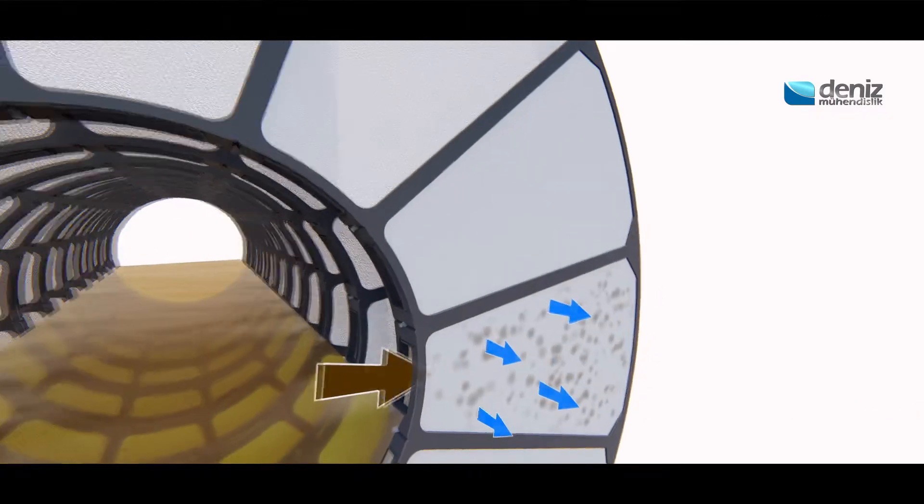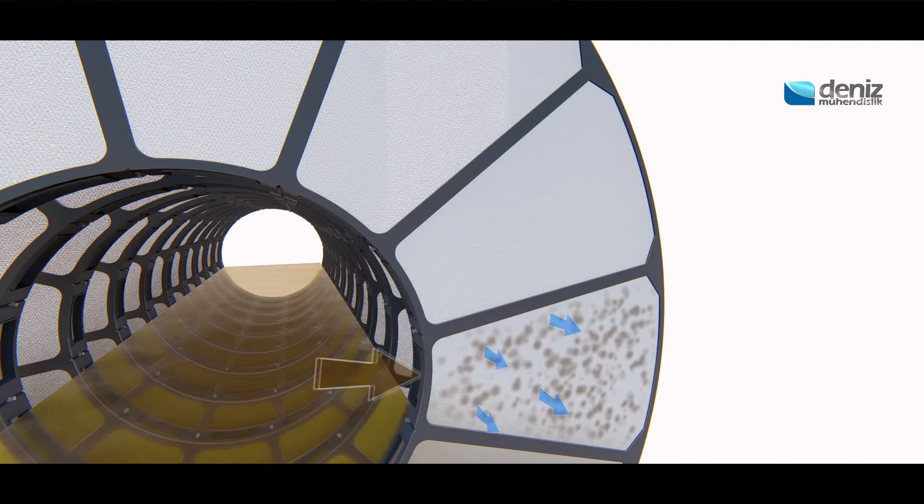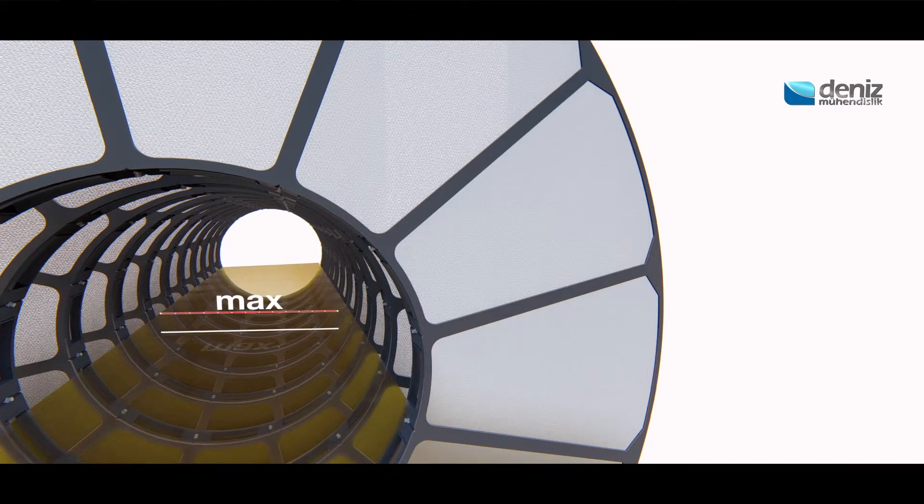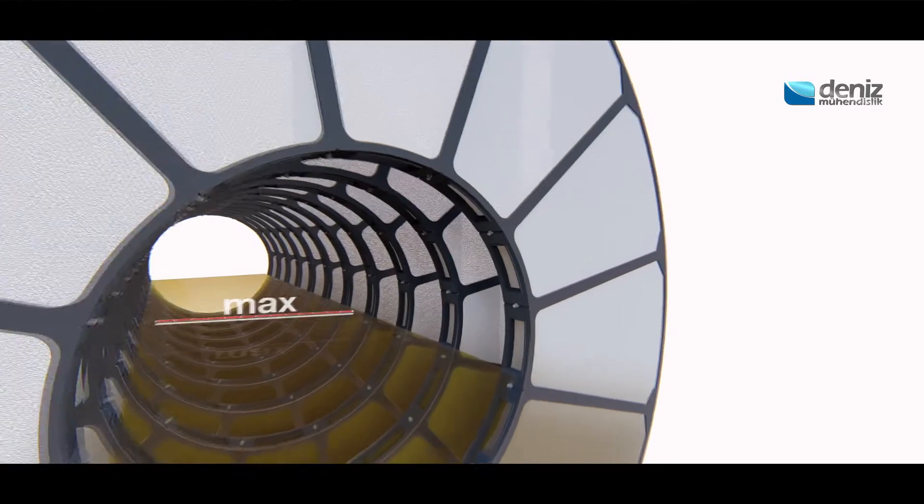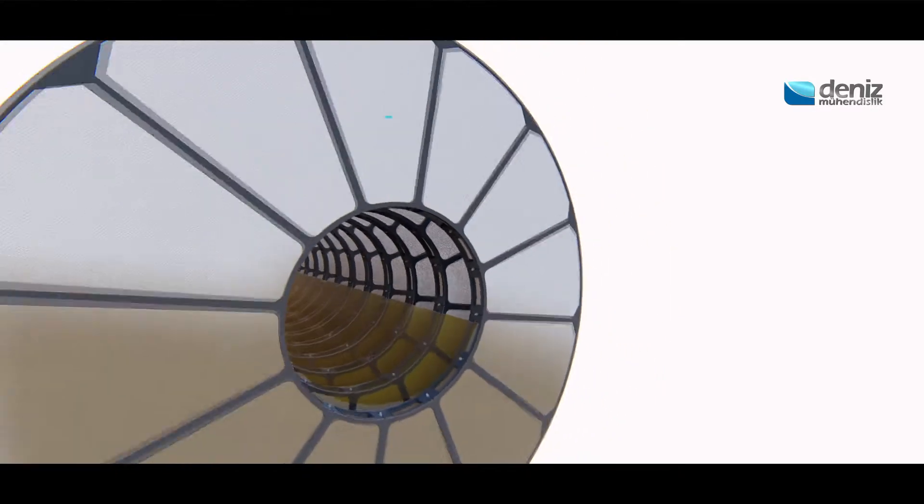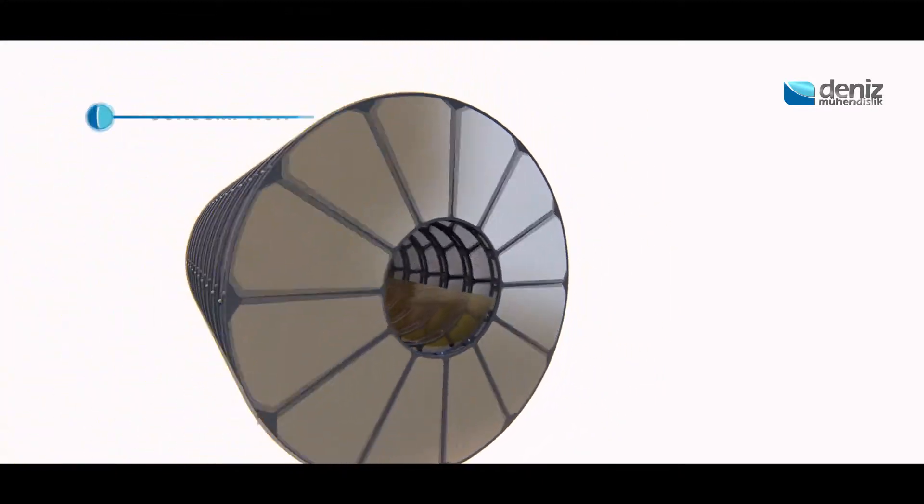As the solids accumulate on the filter cloth, water level inside the main shaft increases. When the water level reaches the preset maximum level, the backwash system engages and the discs start to rotate.